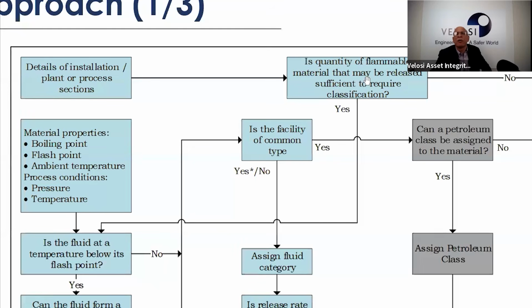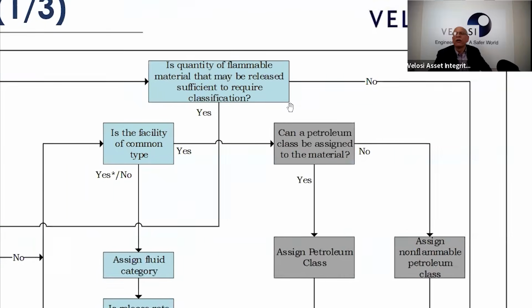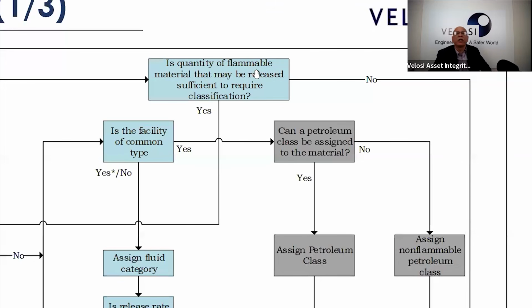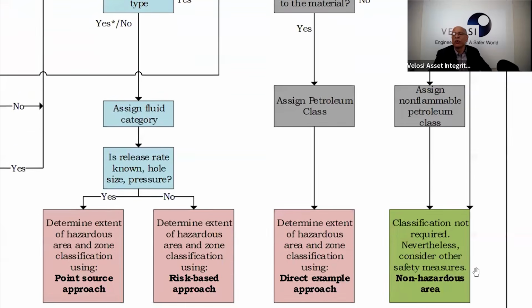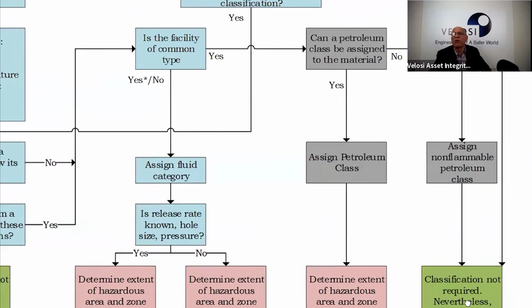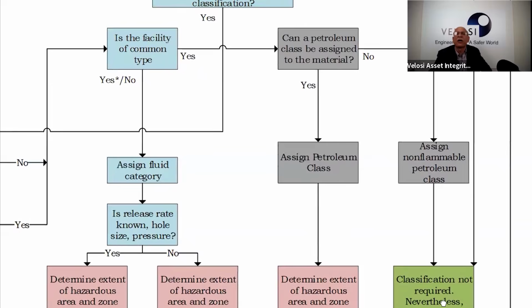Is the quantity of flammable material that may be released sufficient to require classification? If the answer is yes, then we ask, is the facility of common type, like, can a petroleum class be assigned to the material? If no, then classification is not required. Nevertheless, consider other safety measures, non-hazard area. So this is the easy one we have done first, where hazard area classification is not required.